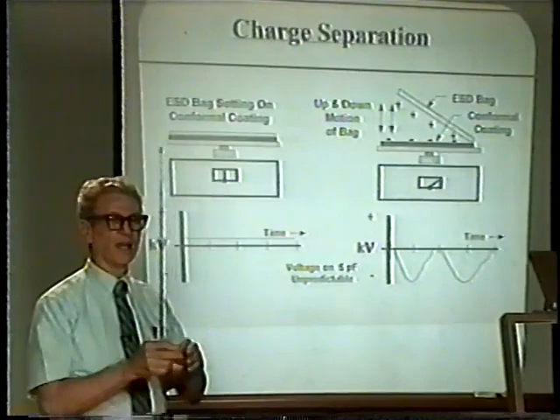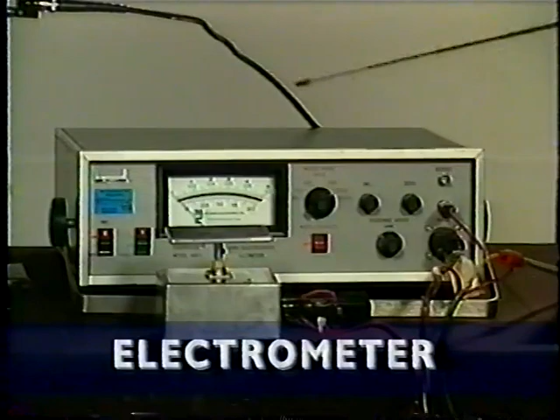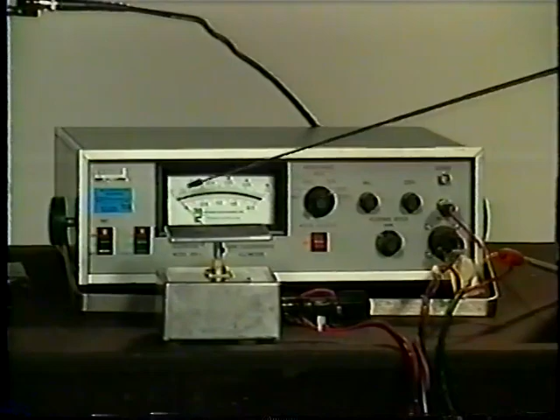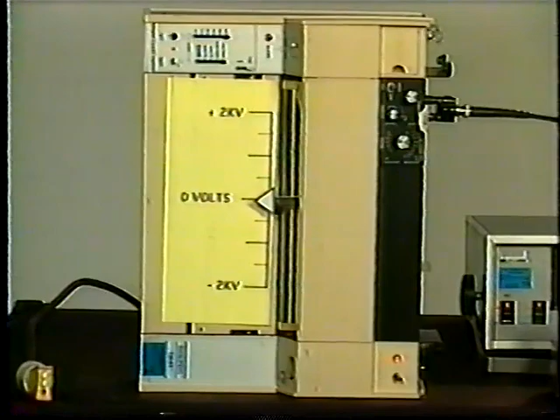I will now explain the equipment making the measurement here on the table. This is the main unit of the electrometer, and the electronics inside decide what voltage it has to provide to the electrometer head. Once it makes that decision and outputs on the meter, we also record it on the chart recorder here, with 0 volts at the center. It goes up to plus 2 kilovolts and minus 2 kilovolts, and now we see an output of the voltage on the electrometer head.